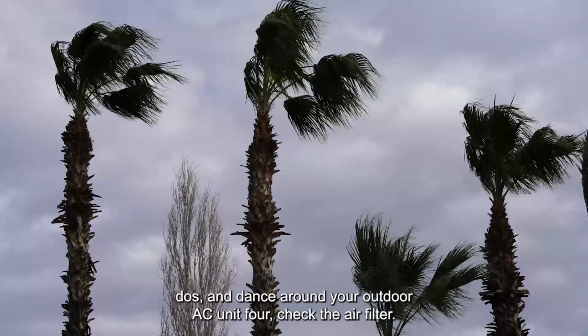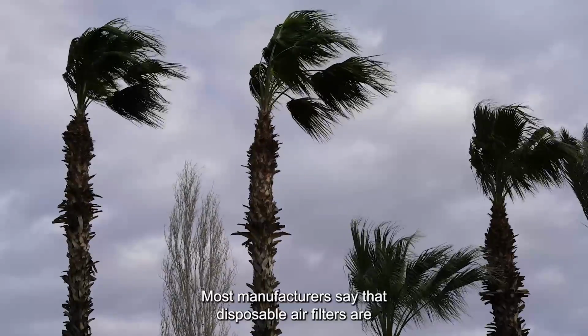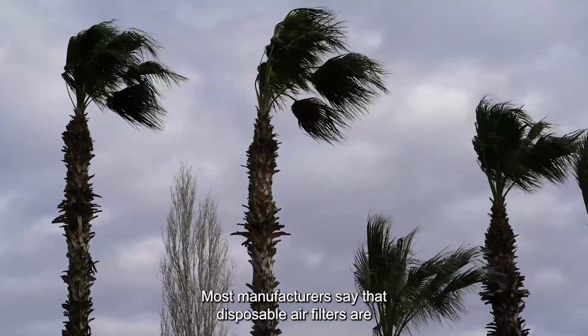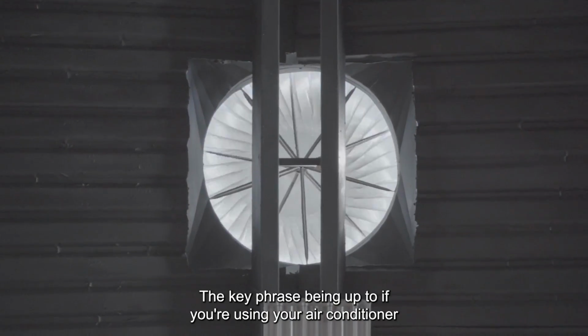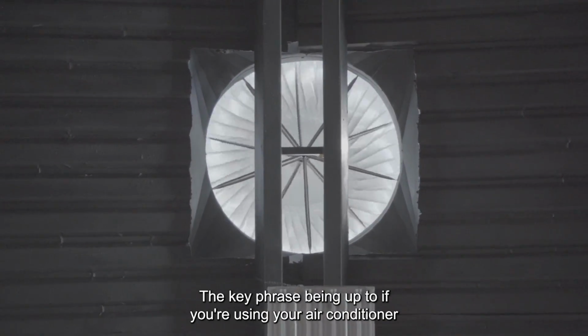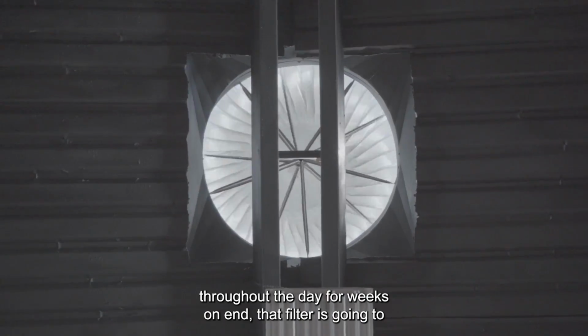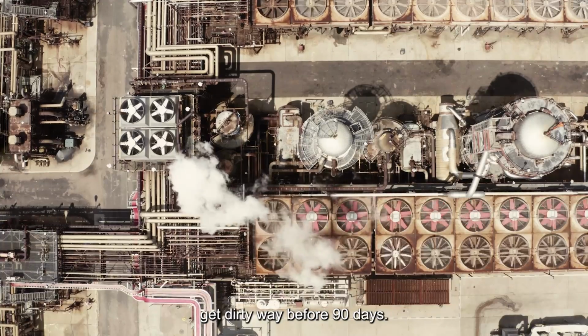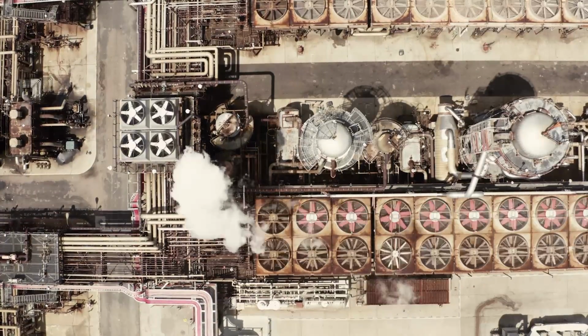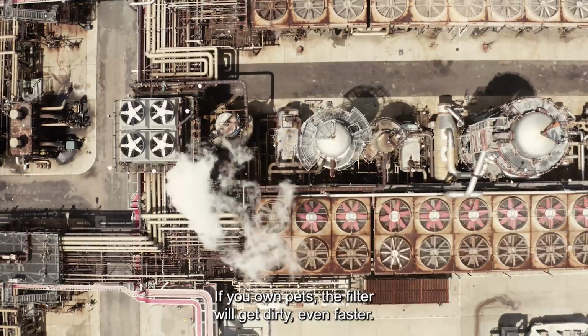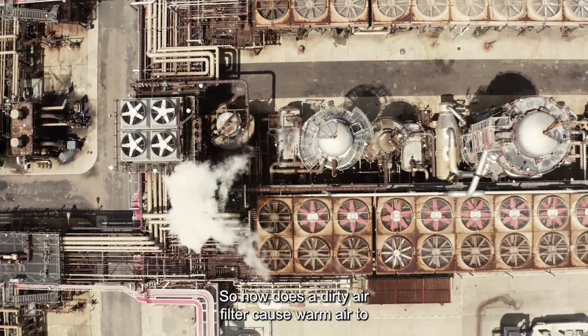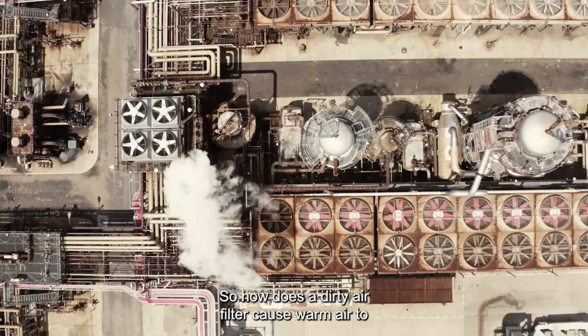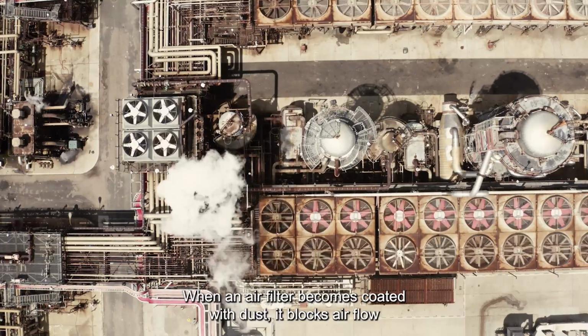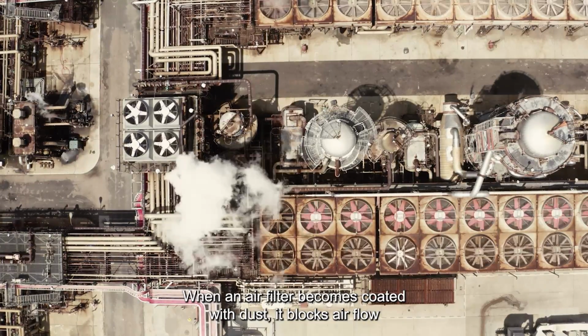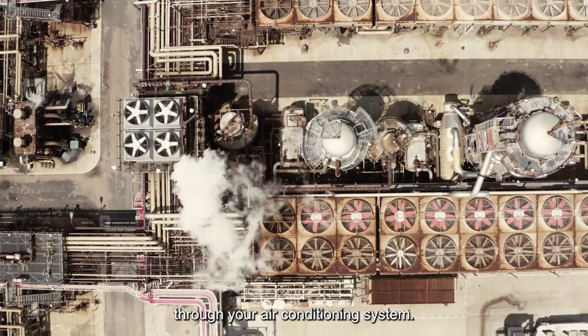4. Check the air filter. Most manufacturers say that disposable air filters are good for up to 90 days, the key phrase being "up to." If you're using your air conditioner throughout the day for weeks on end, that filter is going to get dirty way before 90 days are up. If you own pets, the filter will get dirty even faster. So how does a dirty air filter cause warm air to come from an air conditioner? When an air filter becomes coated with dust, it blocks airflow through your air conditioning system.